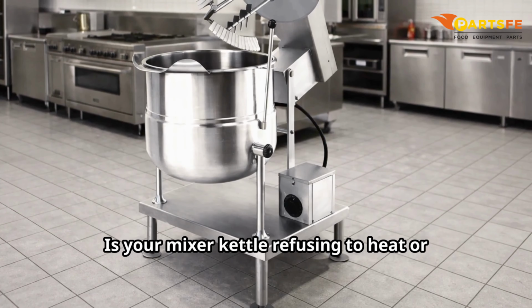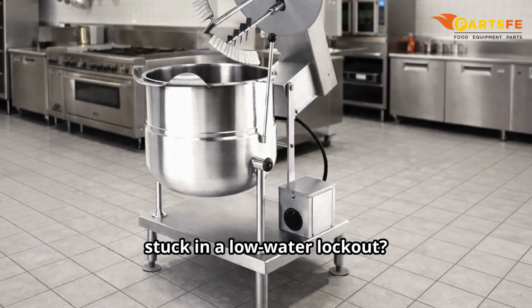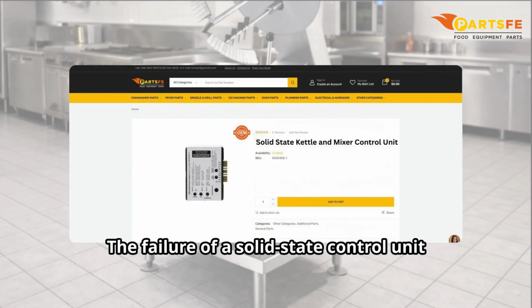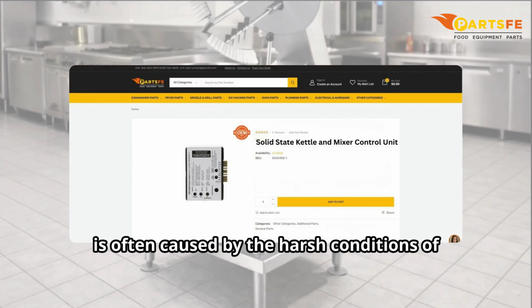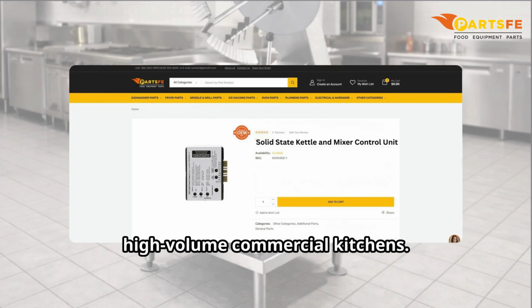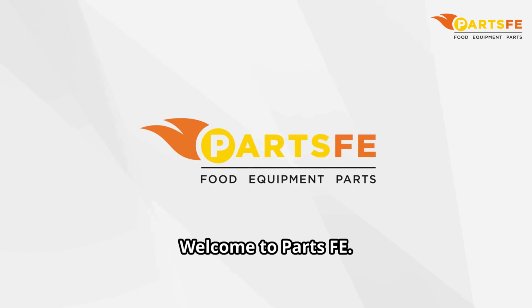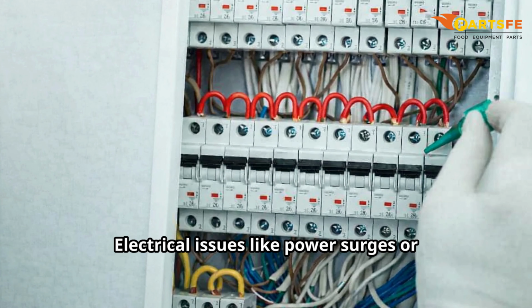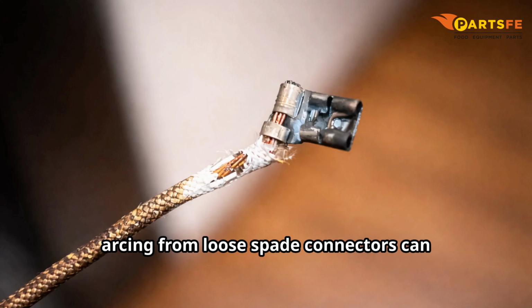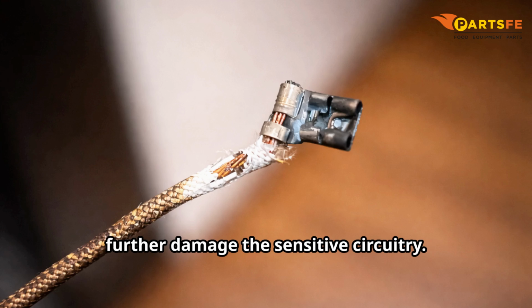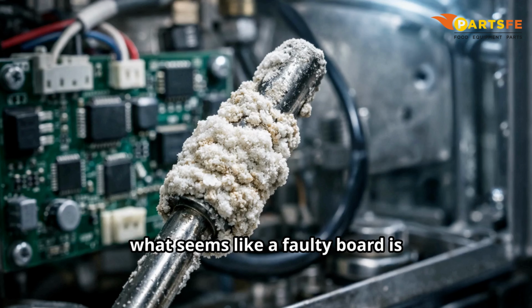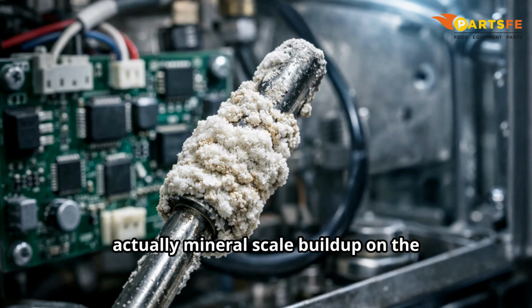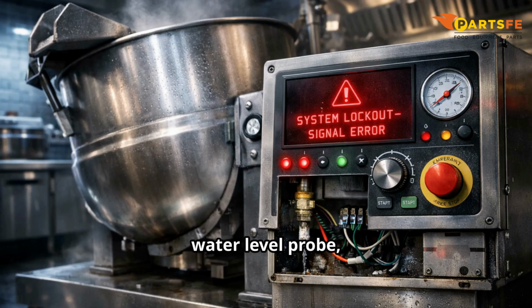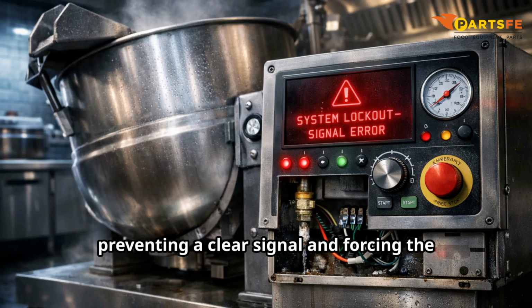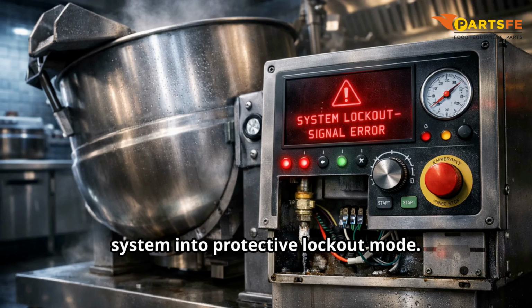Is your mixer kettle refusing to heat or stuck in a low water lockout? The failure of a solid-state control unit is often caused by the harsh conditions of high-volume commercial kitchens. Electrical issues like power surges or arcing from loose spade connectors can further damage the sensitive circuitry. Sometimes what seems like a faulty board is actually mineral scale buildup on the water level probe, preventing a clear signal and forcing the system into protective lockout mode.